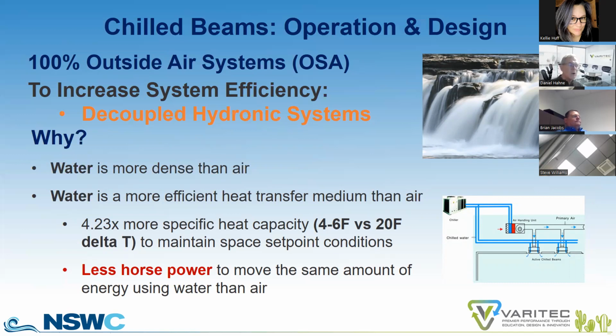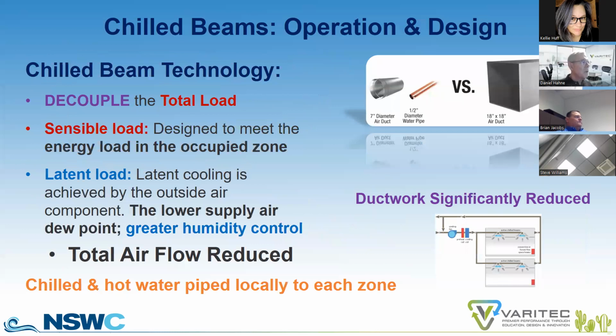Again, to repeat, why? Because water is more dense than air, and water has 4.23 times more specific heat than air. Consequently, you can maintain a space temperature with a 4 to 6 degree chill water differential versus a 20-degree differential in an all-air system supplying 55-degree air to a room conditioned to 75 degrees. So decouple the sensible load from the latent load. Let's bring chill water into all the occupied zones within a building. Let's handle the sensible heat transfer local to each zone. Let's drive as much sensible energy to the chill water loop. And then we'll handle the latent load, supplying the amount of ventilation air required to that building by designing the leaving air condition appropriately. And we'll discuss how to do that.